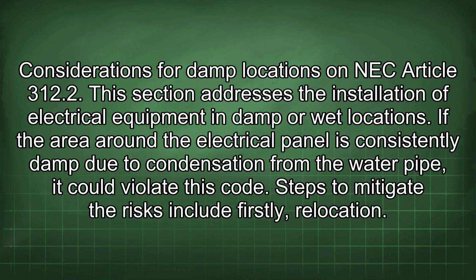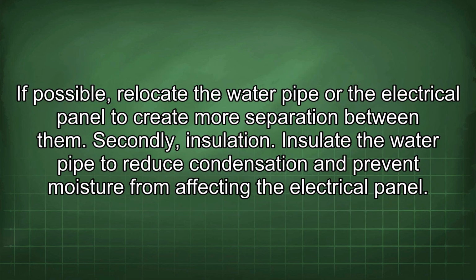Considerations for damp locations on NEC Article 312.2. This section addresses the installation of electrical equipment in damp or wet locations. If the area around the electrical panel is consistently damp due to condensation from the water pipe, it could violate this code. Steps to mitigate the risks include: firstly, relocation. If possible, relocate the water pipe or the electrical panel to create more separation between them.